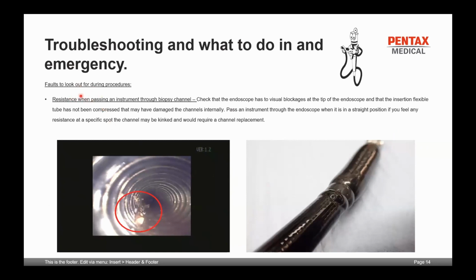Okay, resistance when passing an instrument through the biopsy channel. Things to check: obviously you're going to have a look to see if there are any visual blockages at the tip of the endoscope, as well as at the biopsy inlet where the instrument is passed into the endoscope. Another thing to look at is to make sure that the insertion tube has not been compressed or damaged in any way, which might have then internally caused damage to the biopsy channel.